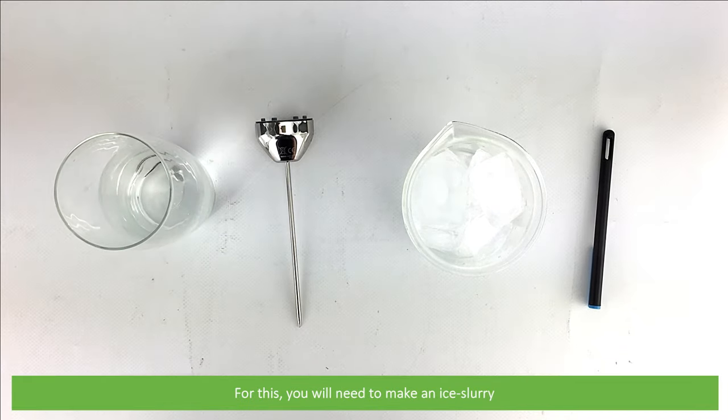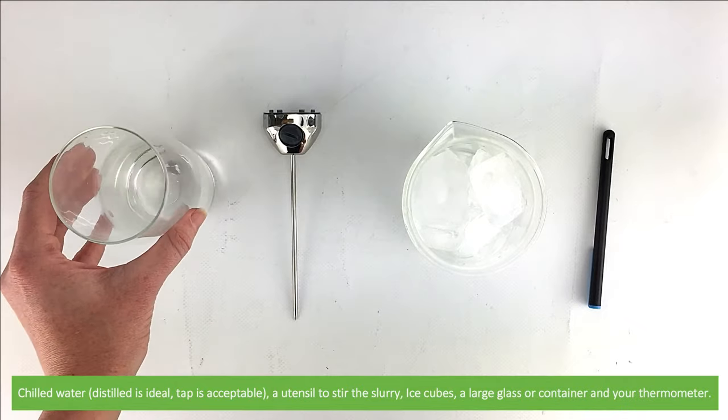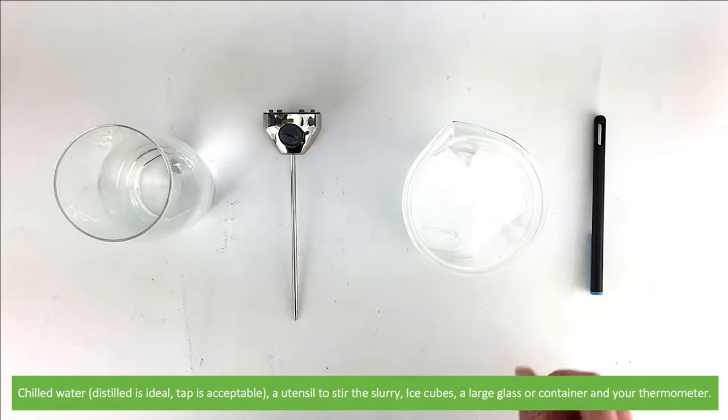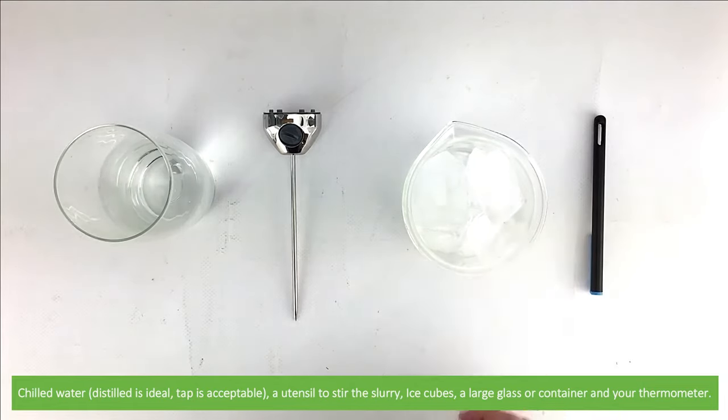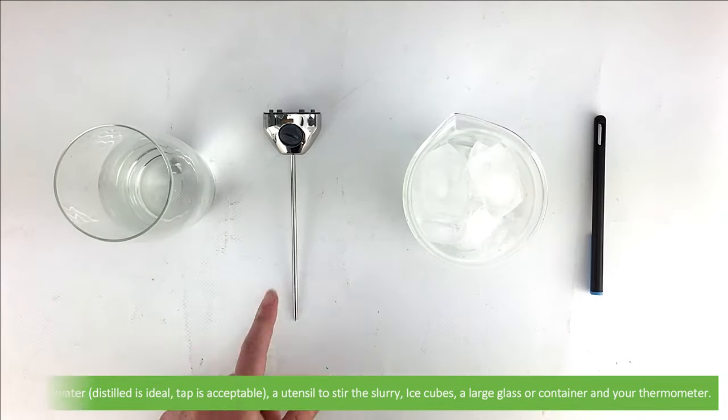For this you'll need to make an ice slurry. To make an ice slurry you will need chilled water, distilled is ideal, tap is acceptable, a utensil to stir the slurry, ice cubes, a large glass or container, and your thermometer.